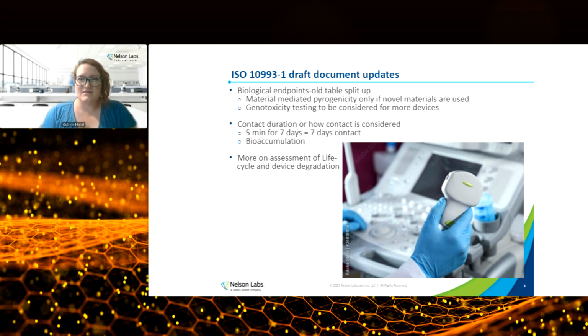There's also more on device degradation, and when that can occur. Before, it was like, oh, my material doesn't degrade, so I don't need to talk about that. But now it wants you to more or less prove that this isn't going to happen with your device, whether that's with functional testing or chemical characterization. There are different ways you can support whether your materials could degrade over the life of the device. So there's a lot more guidance on that as well.